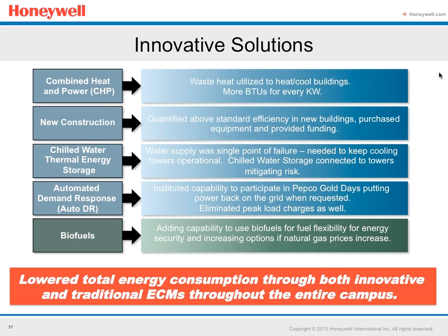Innovative solutions have been applied to White Oak, including combined heat and power. It's not just that we use the heat with an absorption chiller. They determined it would be more efficient and economical to run that steam in the summertime through a steam turbine, generate electricity, and run high efficiency electrical chillers instead. They have the option to do both, but that's now online to make sure they're squeezing every possible BTU out of every nickel they spend.